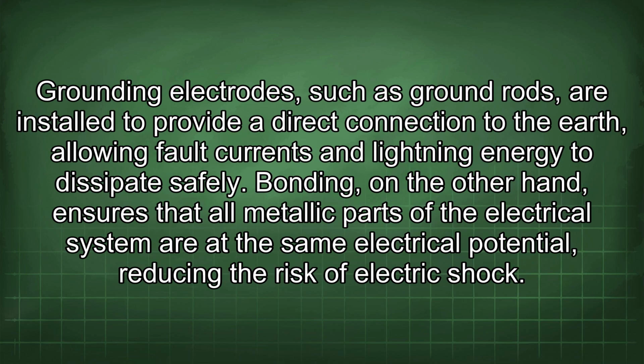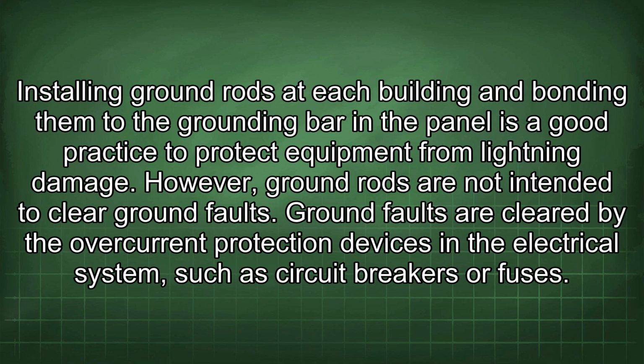Grounding electrodes, such as ground rods, are installed to provide a direct connection to the earth, allowing fault currents and lightning energy to dissipate safely. Bonding, on the other hand, ensures that all metallic parts of the electrical system are at the same electrical potential, reducing the risk of electric shock. Installing ground rods at each building and bonding them to the grounding bar in the panel is a good practice to protect equipment from lightning damage. However, ground rods are not intended to clear ground faults.